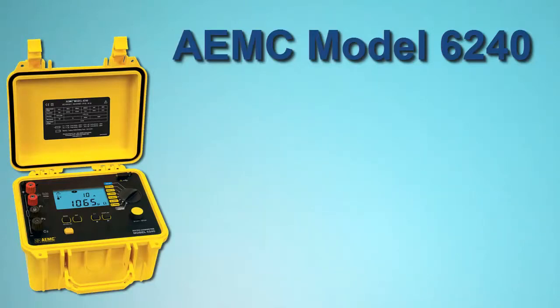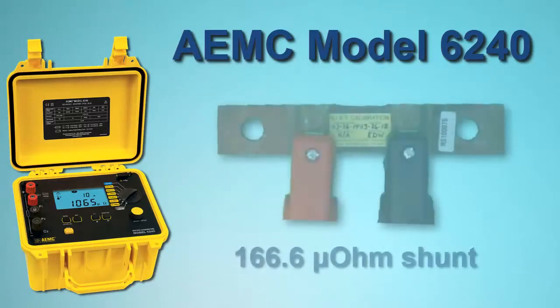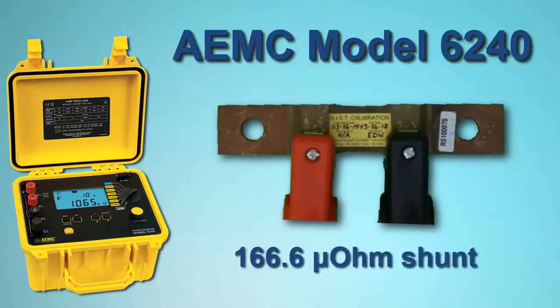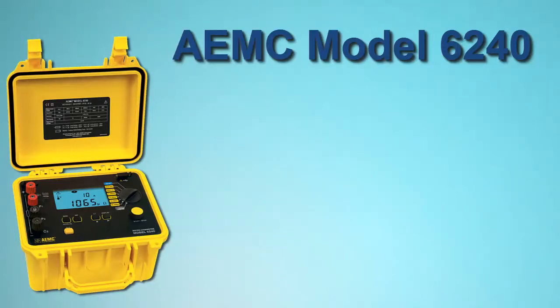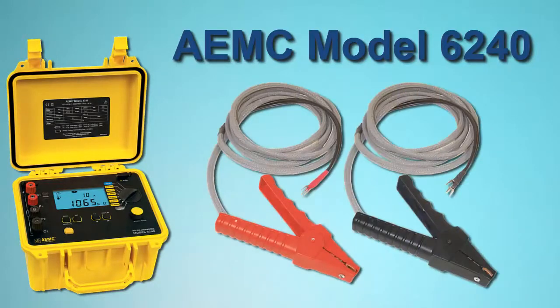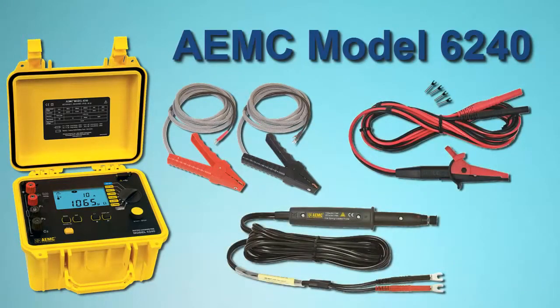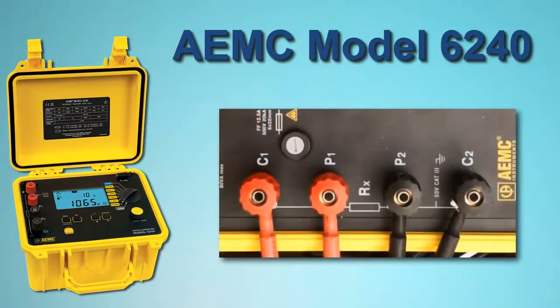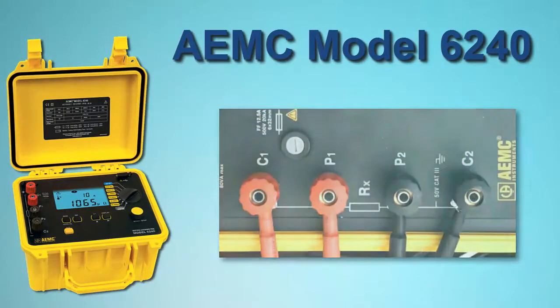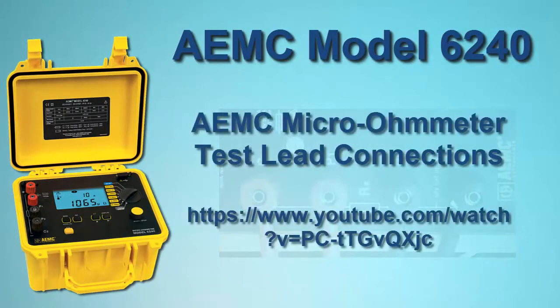For our demonstration, we will connect the instrument to a 166.6 micro-ohm shunt and run a one-minute test with a current of 10 amps. To make the connection, we will use HIPPO type Kelvin clips. The Model 6240 also accepts alligator and spring tip probes. Be sure all leads are correctly attached to the instrument's terminals, as explained in a separate AEMC video.